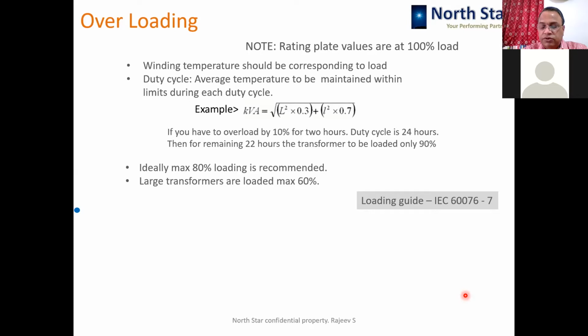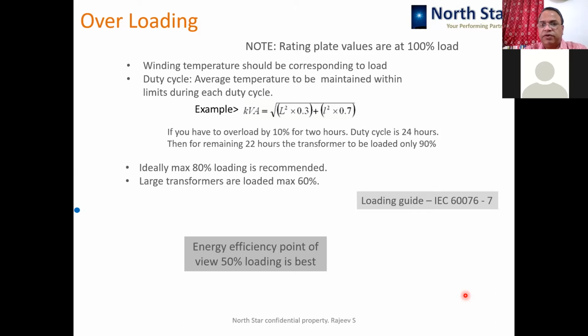Ideally, a transformer should not be loaded more than 80%. In large power transformer situations, even 50 or 60% loading is possible. We all know that a transformer gives its best efficiency somewhere around 45 to 50% loading. But many people feel that is not economical, but we have proven with calculations, and in some other programs we have shared information, that when you load the transformer around 40 to 50%, you actually end up saving a lot of money. That will be somewhere next time, not today.